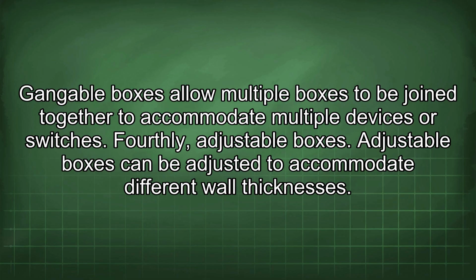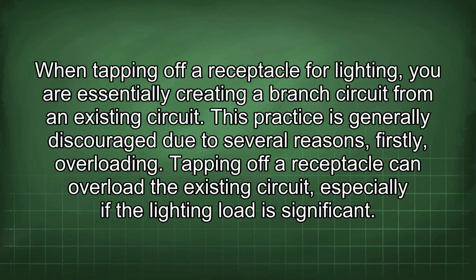Gangable boxes allow multiple boxes to be joined together to accommodate multiple devices or switches. Fourthly, adjustable boxes. Adjustable boxes can be adjusted to accommodate different wall thicknesses. When tapping off a receptacle for lighting, you are essentially creating a branch circuit from an existing circuit. This practice is generally discouraged due to several reasons.